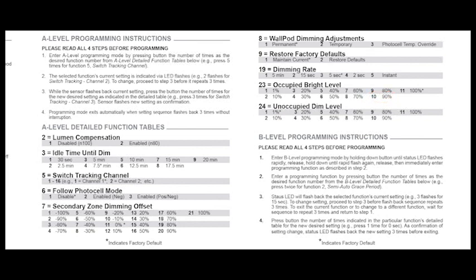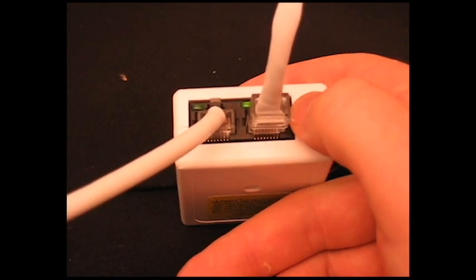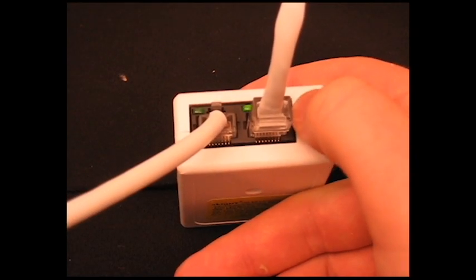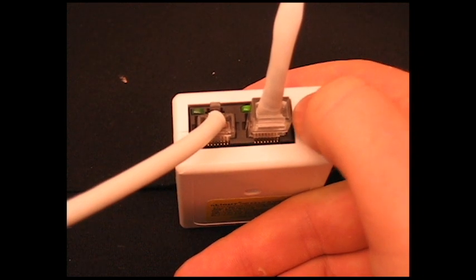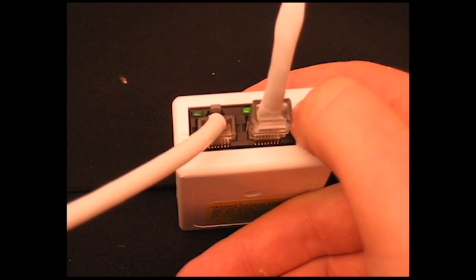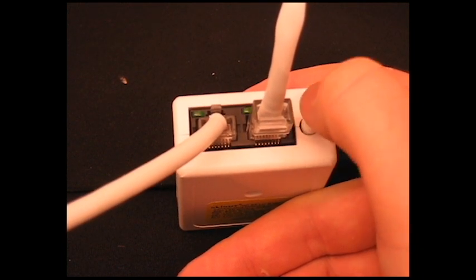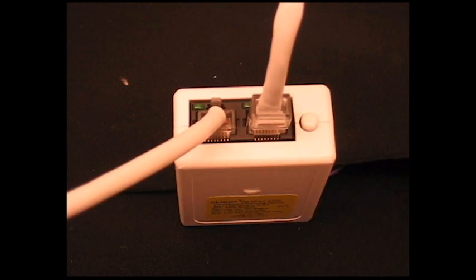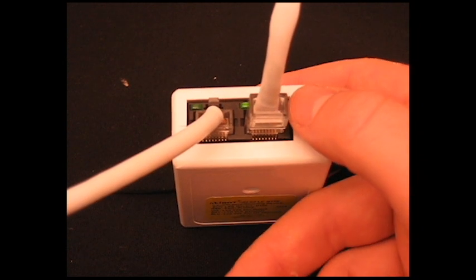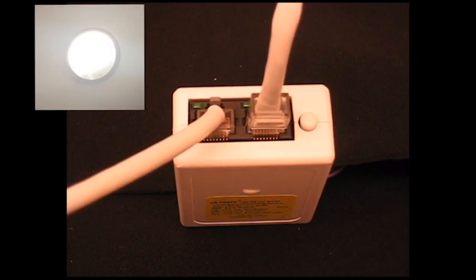For demonstration purposes, let's bring the level down to 10% so we can visually confirm our programming changes. Again, enter Occupied Bright Level programming by pressing the user button 23 times. Before the LED cycles three times, press the button again the number of times that corresponds to our new setting of 10%, which will be twice.